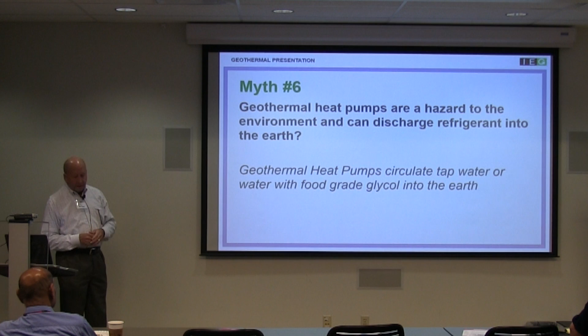In that season of their manufacturing, they decided to re-engineer the U-bend. I ended up talking to the engineer that designed it, and he failed to consider the weight of the water — the column of water sitting on that U-bend. He was just thinking of a horizontal pipe. I told him, no, you've got a 250-foot column of water standing on top of you. So they had global failures with that U-bend design.